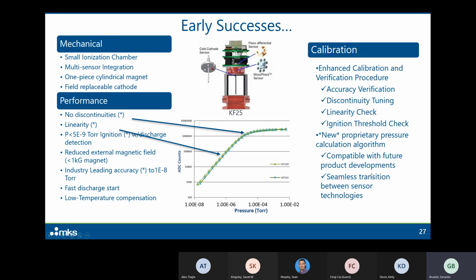And while we're at it, we redesigned the way in which we did the pressure calculation so that we would have flexibility to make changes to the design and not have to completely redo our firmware and software that is built into the instrument, while at the same time also providing a seamless transition between the sensor technologies.